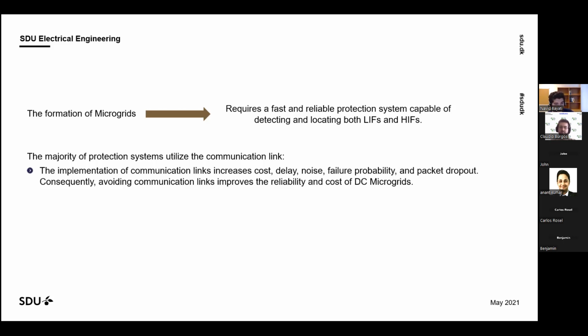So we have a lot of controllers for the whole system, and we have island detection at the connection between the grid and the microgrid. When we have islanding, the settings of the control systems in the microgrid will change to island mode. One of the largest production units in the microgrid will go to slack mode, and then we can keep control of the frequency of the system. And also for the voltage, we have the same.